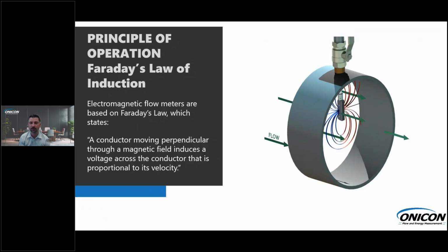So how does this flow meter work? It's using Faraday's law. If you remember physics class back in the day, we're creating a magnetic field and putting a conductor, in this case water, through that magnetic field, and it's creating a voltage. We're measuring that induced voltage, and that's proportional to the velocity going through the system.